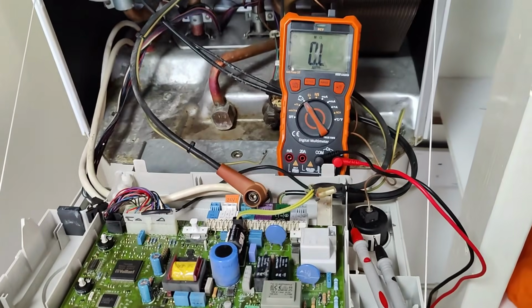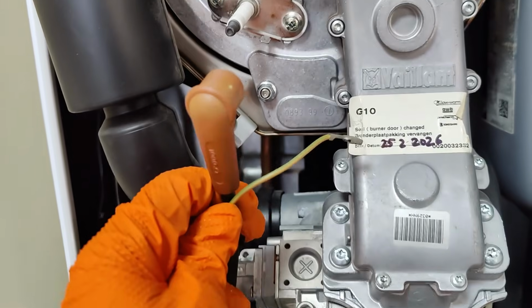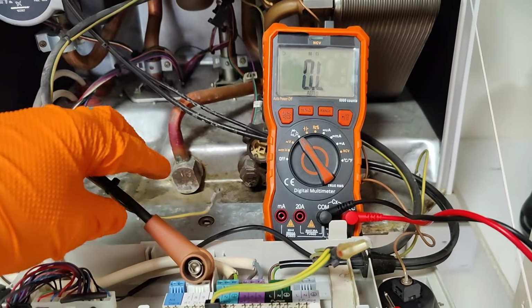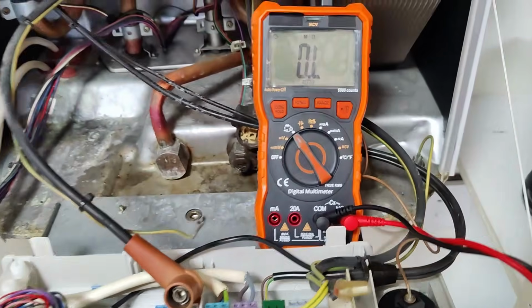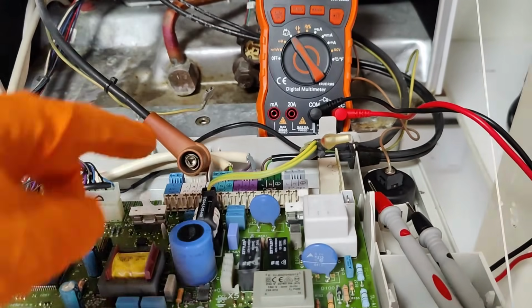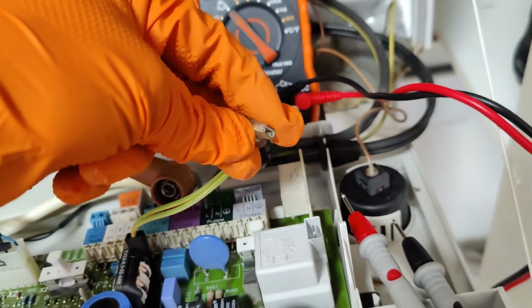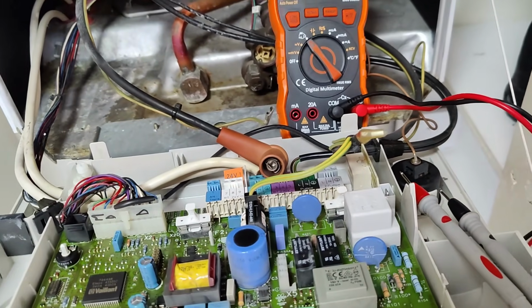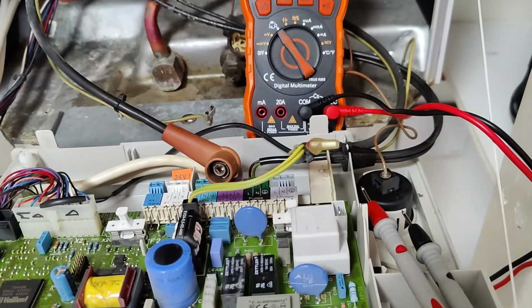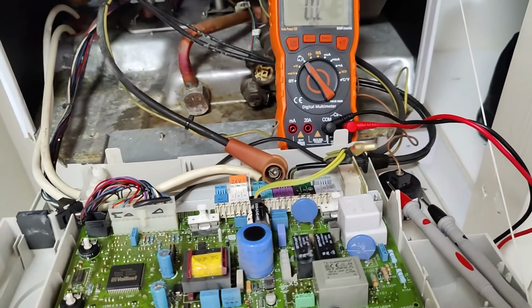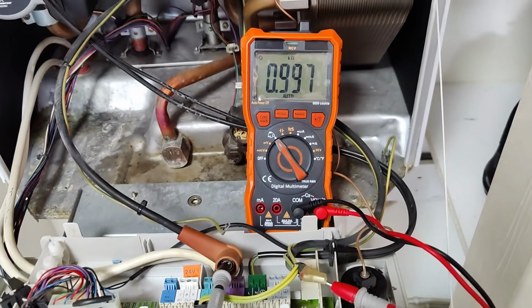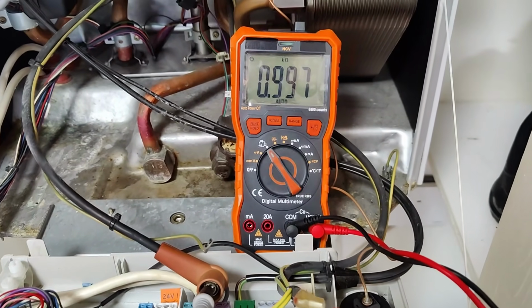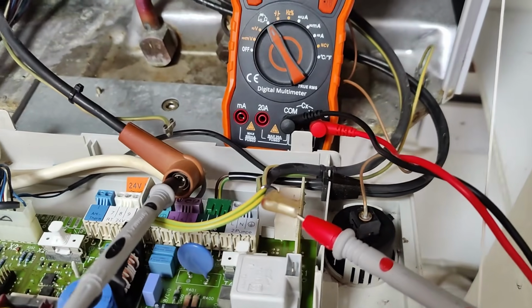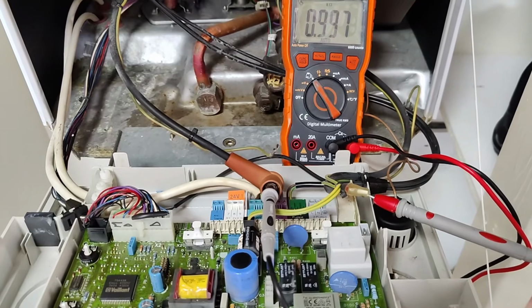Okay, so boiler safely isolated. I've disconnected the ignition probe, the ignition lead from the igniter, and the other end from the actual ignition transformer. I've got my multimeter set to ohms setting, and I'm just going to check between the actual head of the lead and the connector that was connected to the transformer. I'm expecting around 0.9 kilo ohms or 900 ohms reading, something in the region of that. That will confirm that our lead is perfectly fine. Let's do the test. Okay, so as you can see, we have 0.99 kilo ohms resistance on the ignition lead, which is perfectly fine.